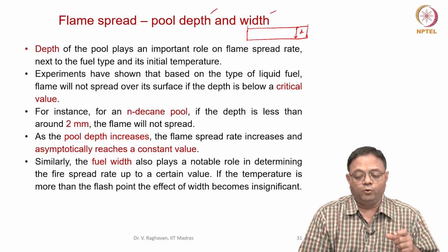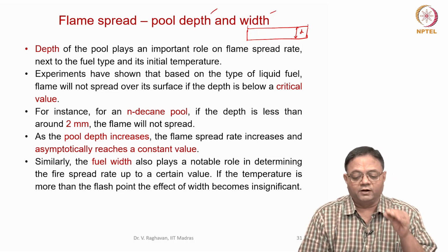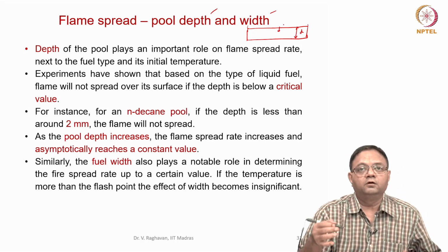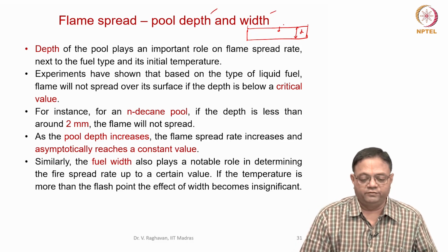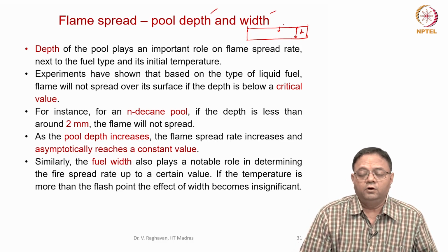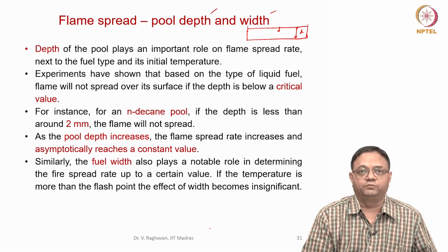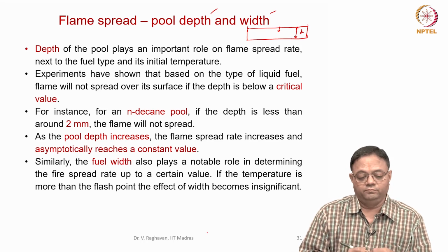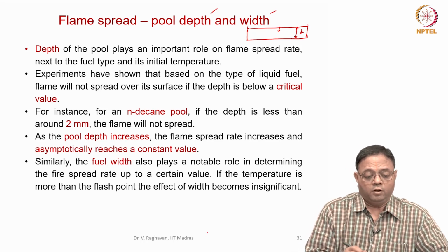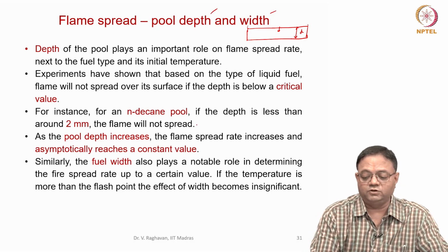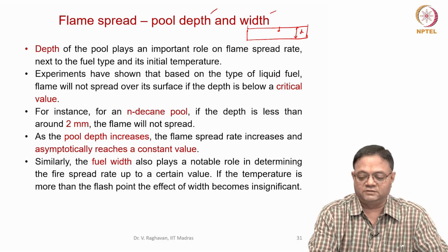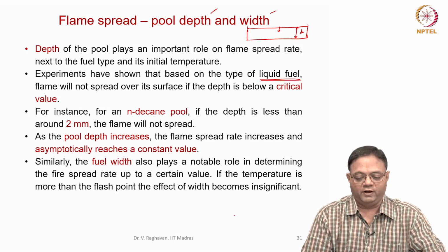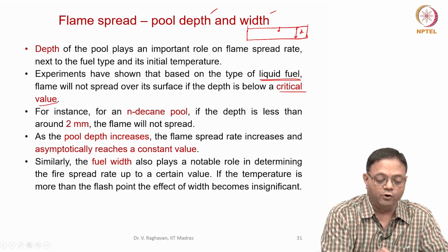So when you have a certain depth, there is a certain heat transfer to the liquid phase. If you have very low depth, then the flame need not propagate. Experiments have shown that based on the type of liquid fuel, again characteristics of liquid fuel like its volatility, flame will not spread over the surface if the depth is below a critical value.